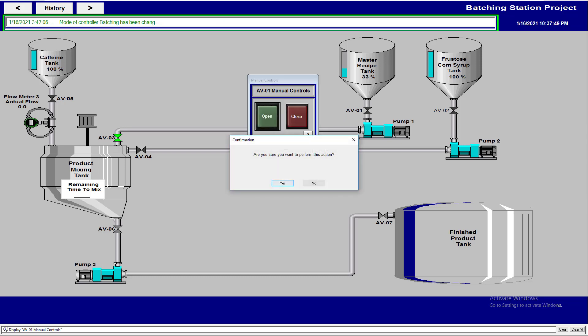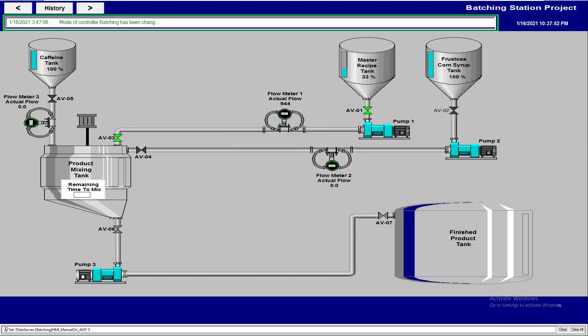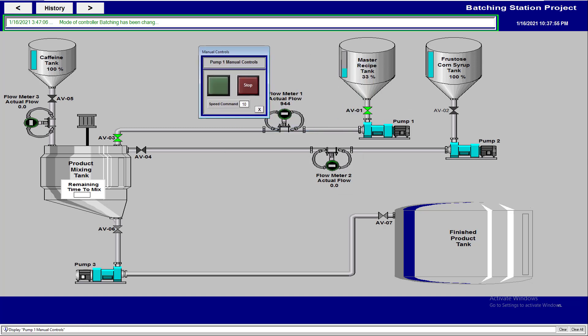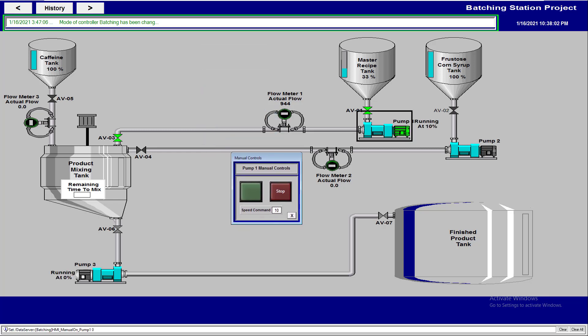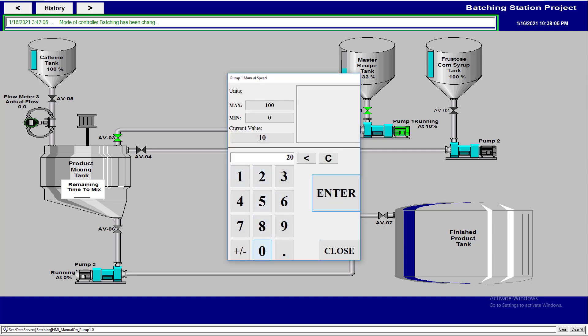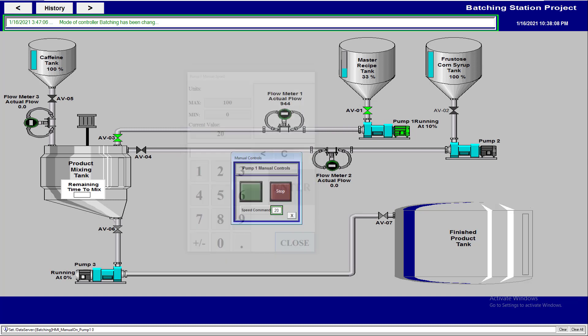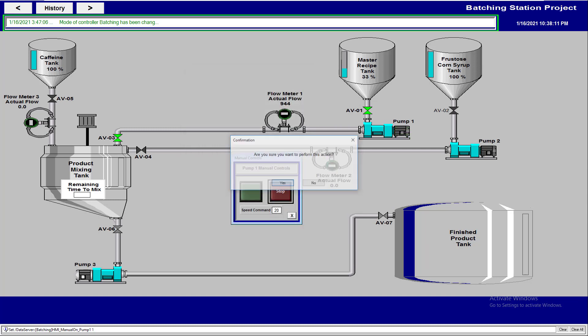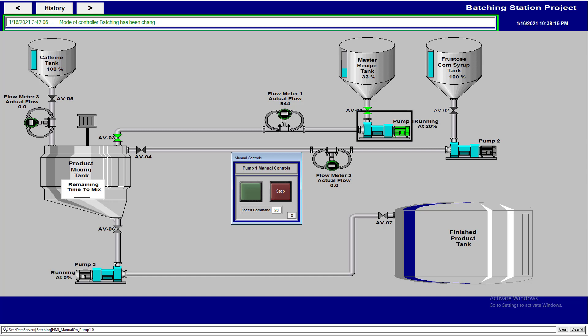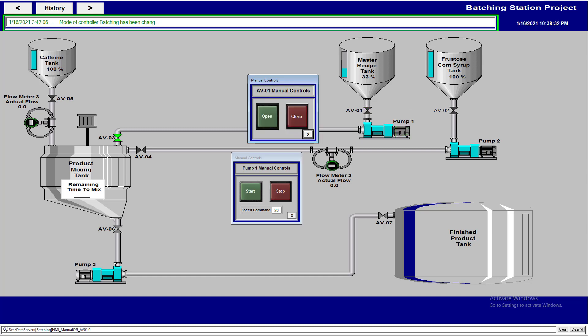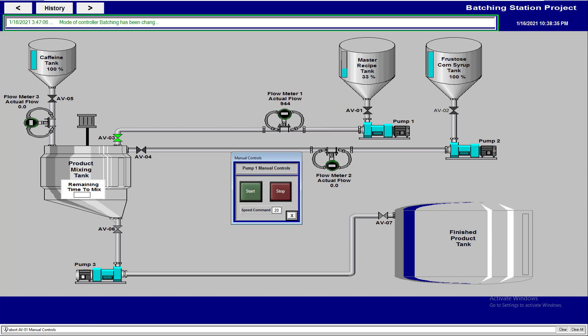Later we can populate an alarm to say 'you need to turn on AV01 and AV03.' If I toggle AV03 on and turn on AV01, then I turn my pump on — now my pump runs at 10. If I change the speed it will not change on a servo, because we have to stop and start it, then it will change to 20. There is a dynamic update option for servos, but we're just running at a set speed.